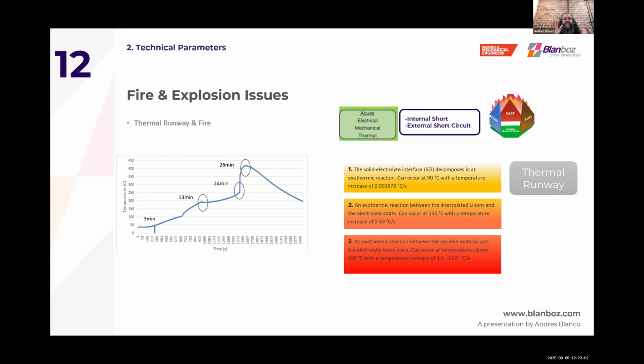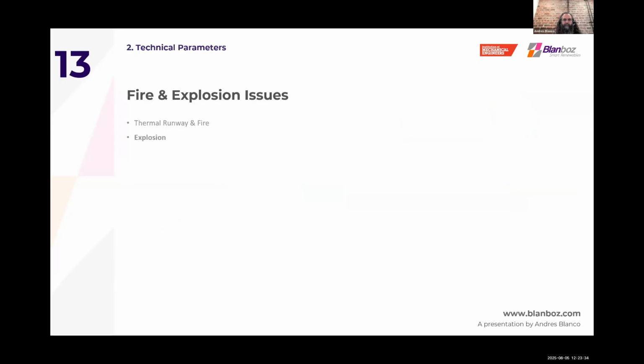Pretty much what that means is combustible gases are being generated and released within the battery container. From the off-gassing to fire, actually you don't have much time. It's around 10 to 13 minutes. That's why we need to rely on sensors, first of all, to alert us and to have some precautions of how we can minimize, hopefully, the fire, so that it doesn't happen, or to reduce the risk, and also to alert us to trigger the emergency response plan.